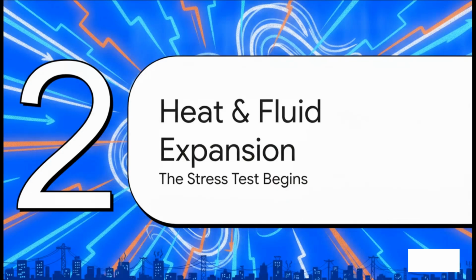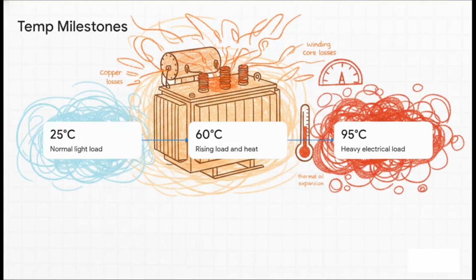The stress test begins. Picture this. As the city wakes up and power demand surges, the electrical load on the system gradually increases. Because of what engineers call copper and core losses, which is basically just the unavoidable resistance and magnetic friction generated by electricity, the transformer starts generating continuous, intense heat. We can track this climbing steadily. We start at our perfectly calm 25-degree baseline, push up to 60 degrees as the morning load rises, and finally hit a blistering 95 degrees Celsius under heavy peak electrical load.